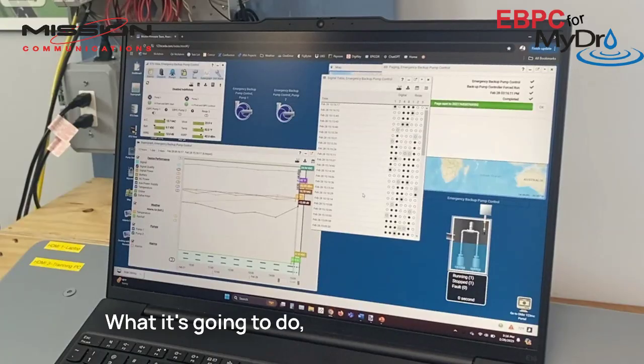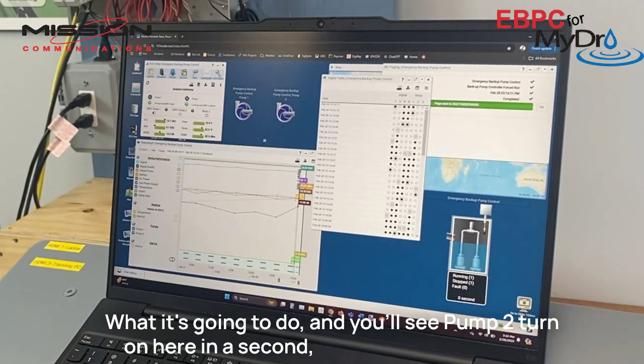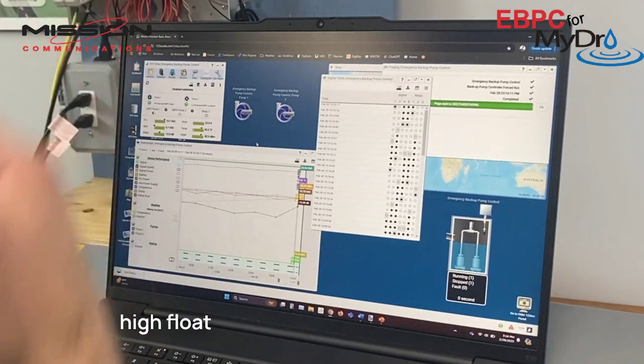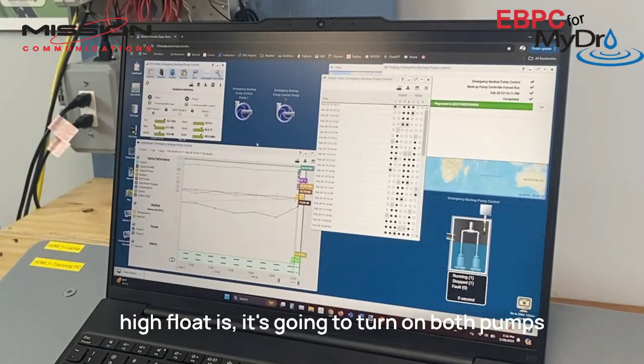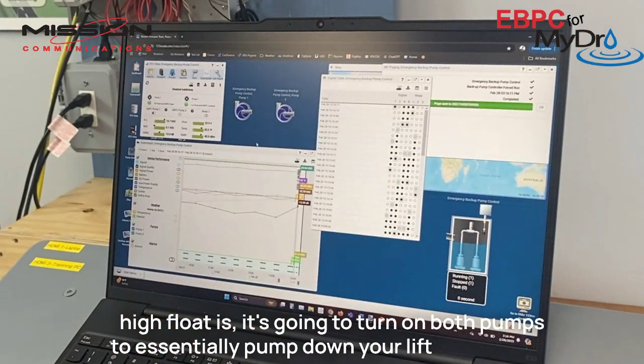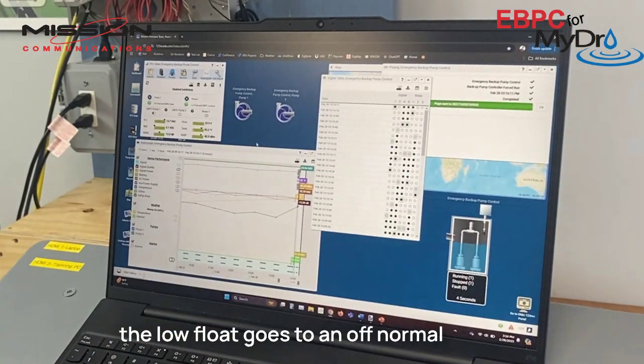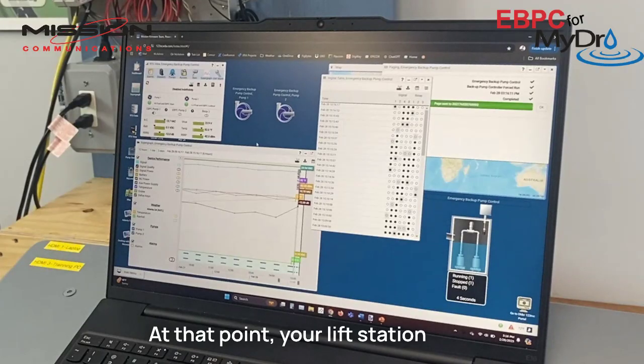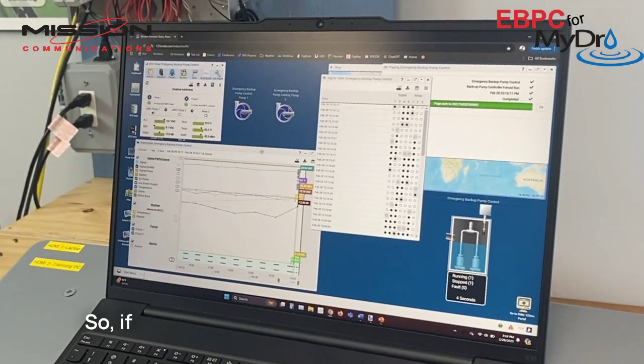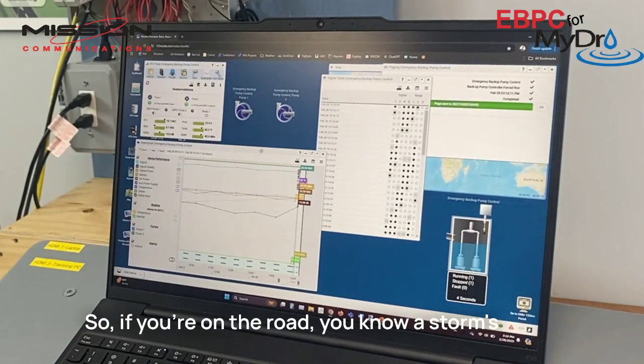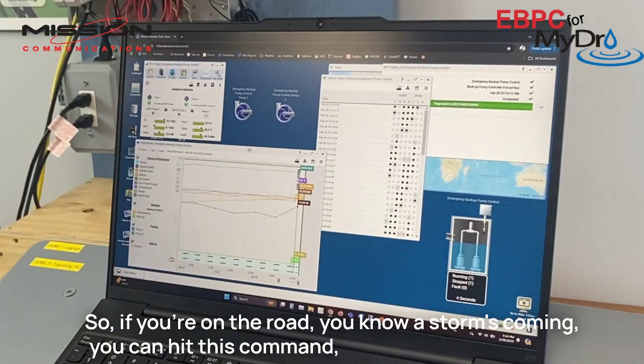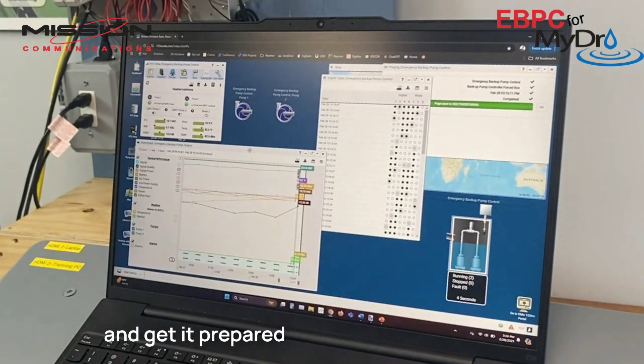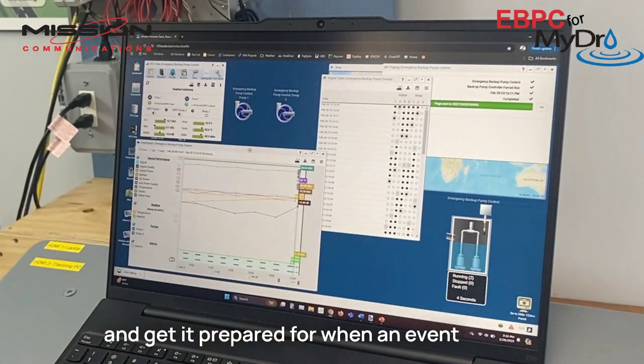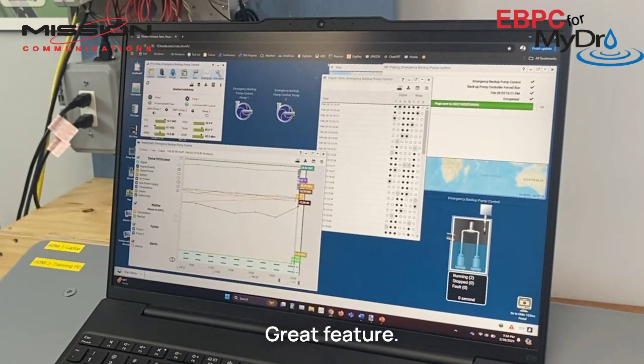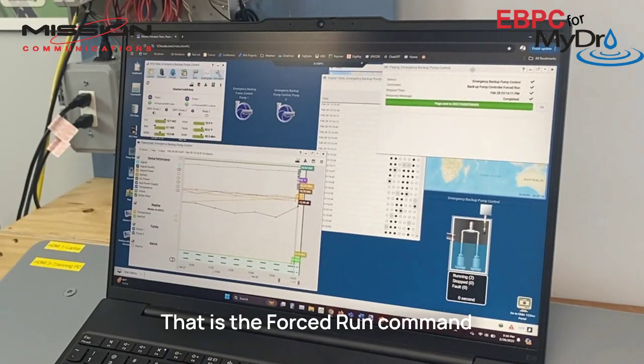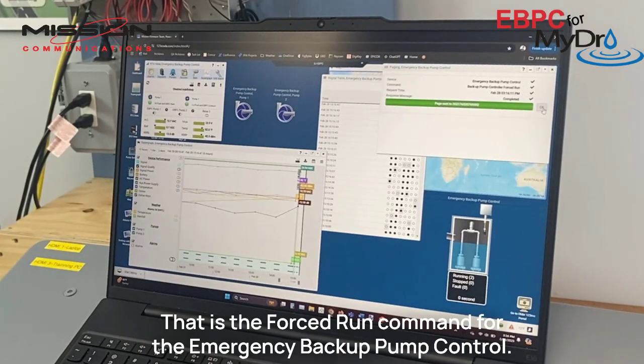And what it's going to do, and you'll see pump 2 turn on here in a second, is no matter where that high float is, it's going to turn on both pumps to essentially pump down your lift station until the low float goes to an off normal condition. At that point, your lift station is empty. So if you're on the road, you know a storm's coming, you can hit this command, pump down your station, and get it prepared for when an event is coming. Great feature. That is the force run command for the emergency backup pump control.